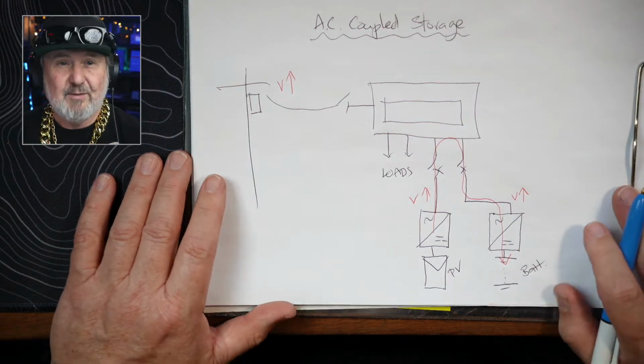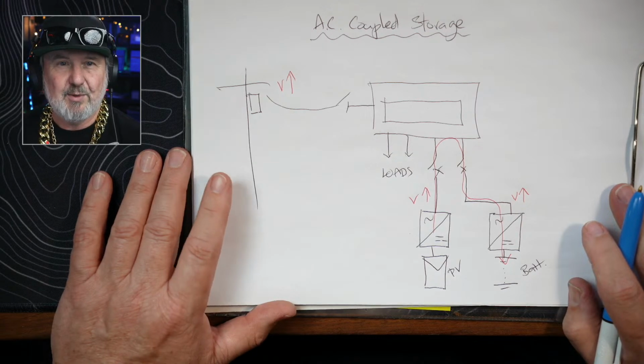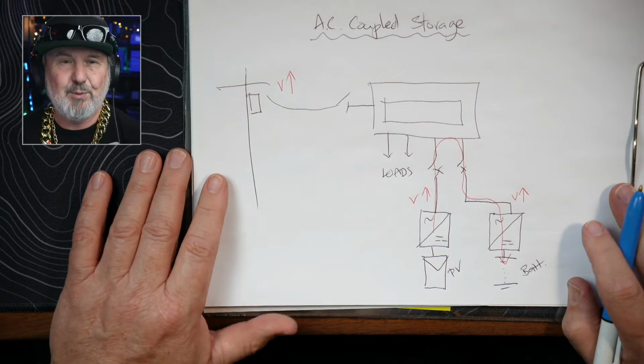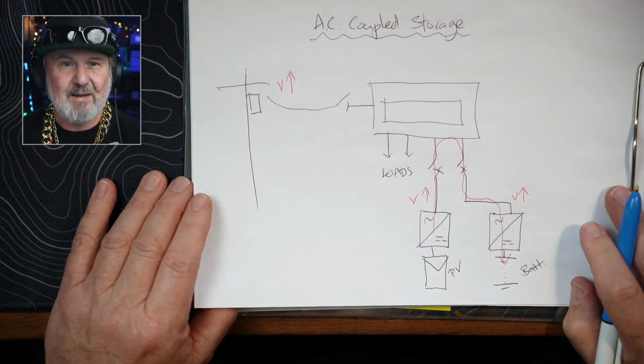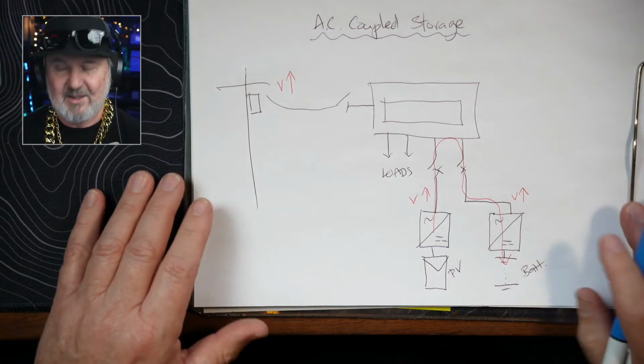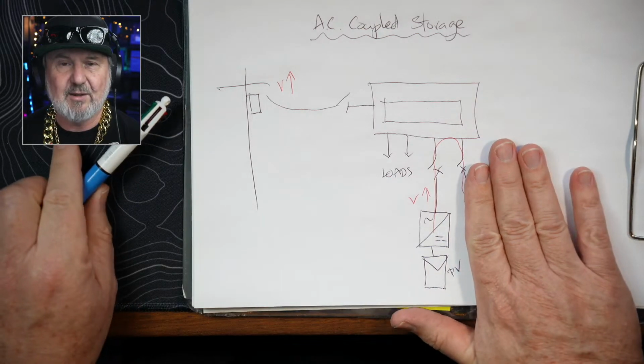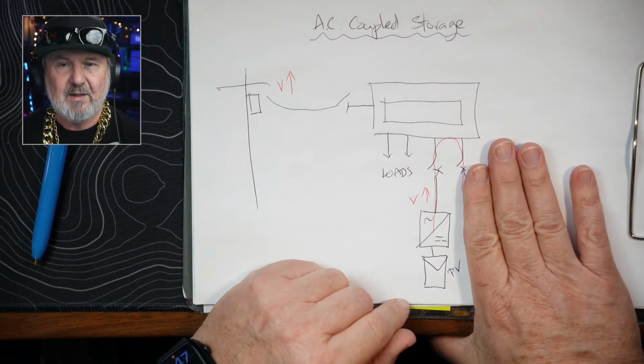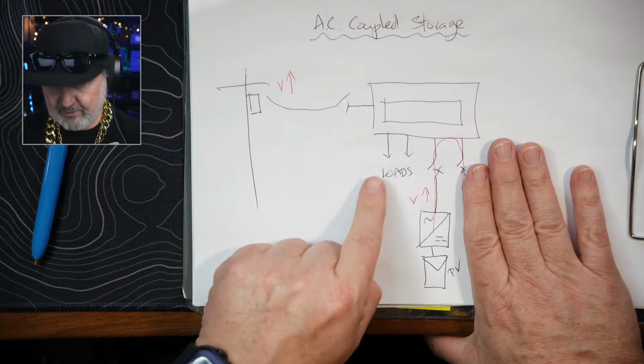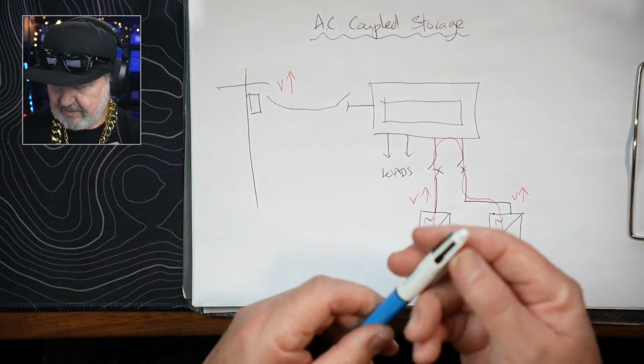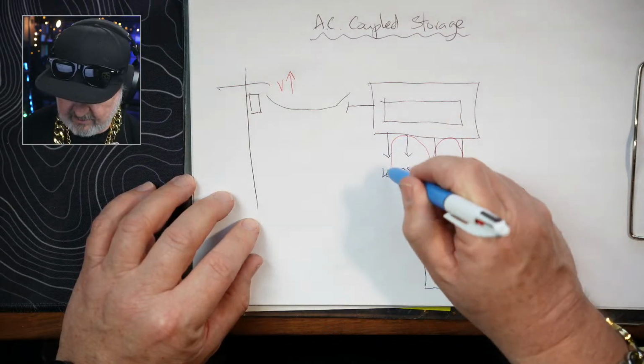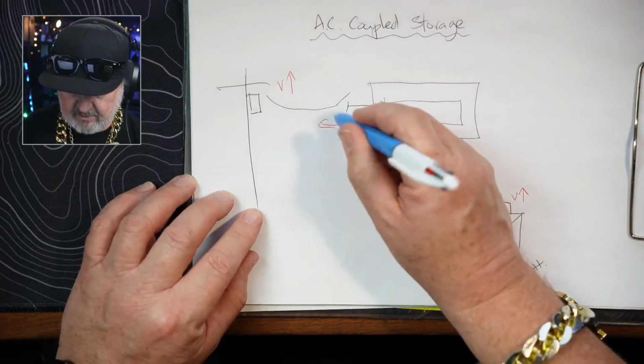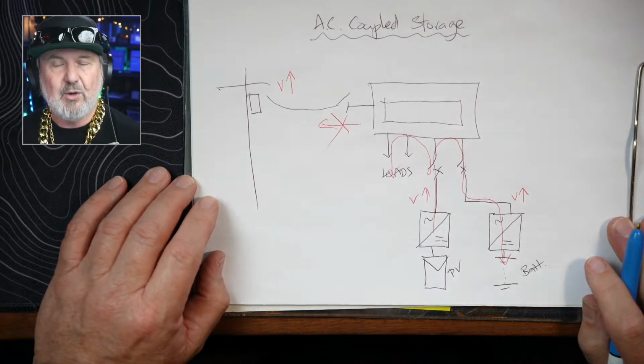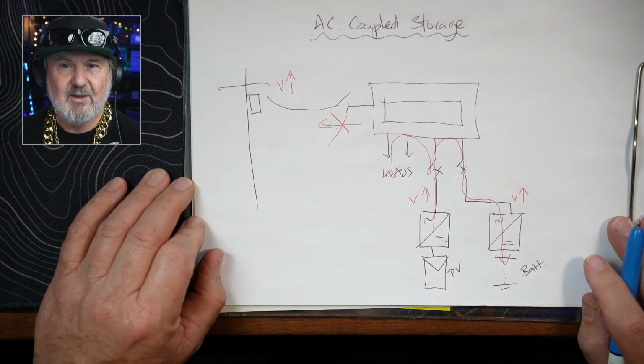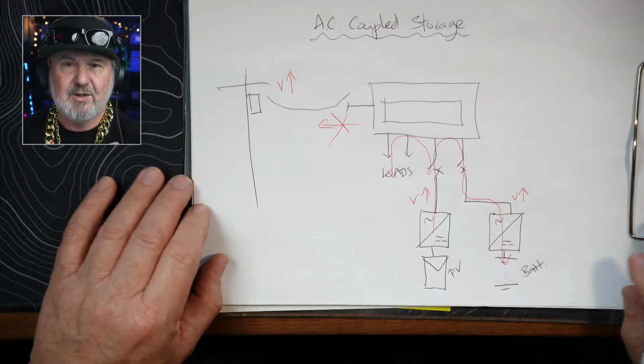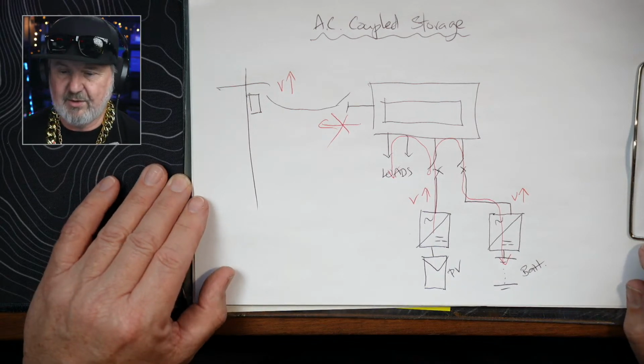There is kind of a third way to help reduce this problem. It's probably the simplest one, which is put more load on. Don't export power. So if your inverter's shutting down, and let's say you don't even have a battery, you just got a solar installation like this, if you put more loads on, then the power is going to be going to the loads and not to the grid, and therefore it won't be pushing the grid voltage higher. So that can help as well. So synchronizing loads with the grid.